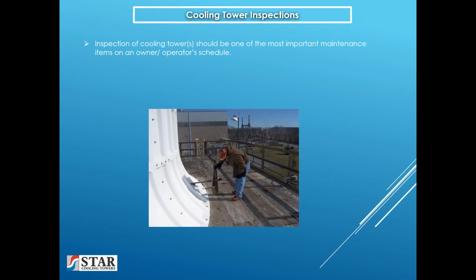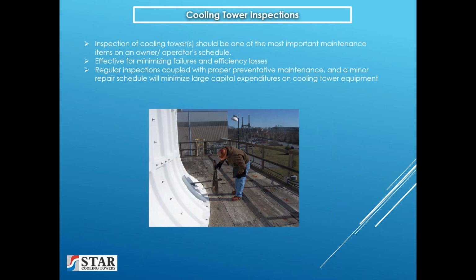Inspection of cooling towers should be one of the most important maintenance items on the owner-operator's schedule. It's effective for minimizing failures and efficiency losses. Regular inspections coupled with proper preventative maintenance and a minor repair schedule will minimize large expenditures on your cooling tower equipment. But remember, the outcome of the inspection is directly related to the competency of the individuals performing the inspection.